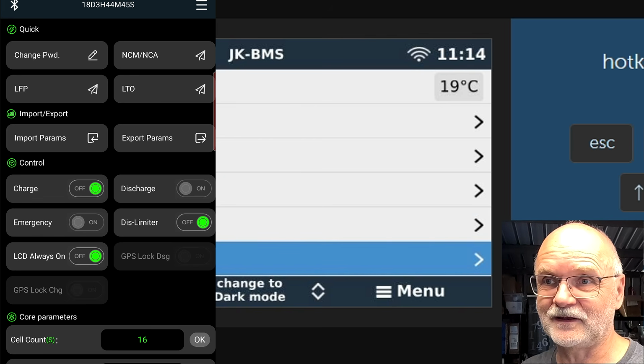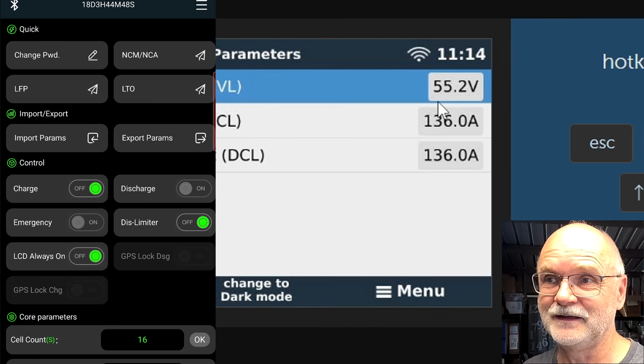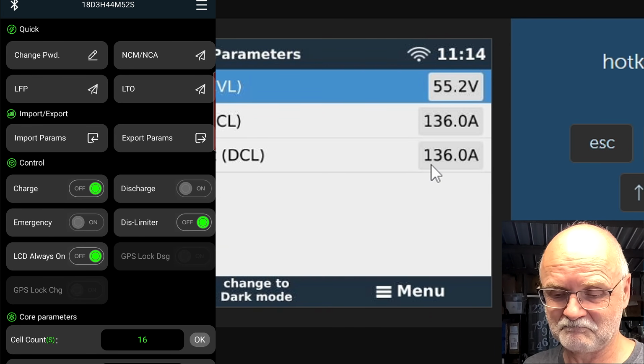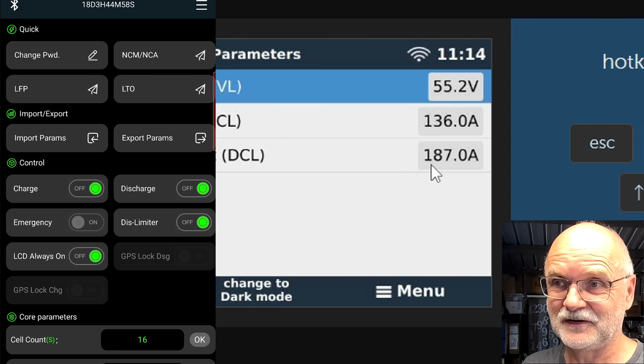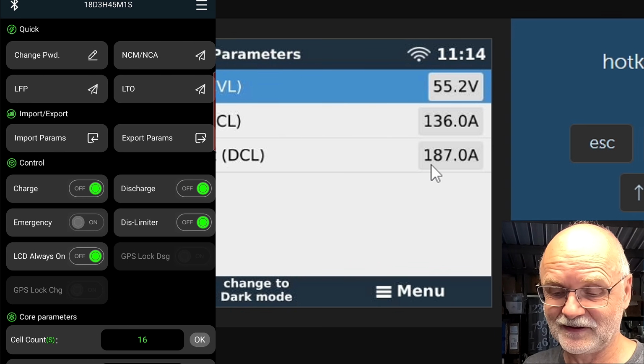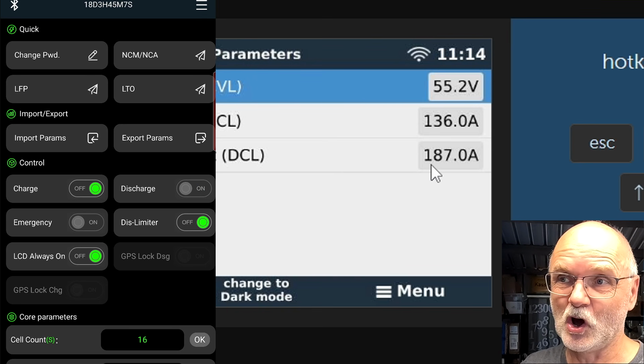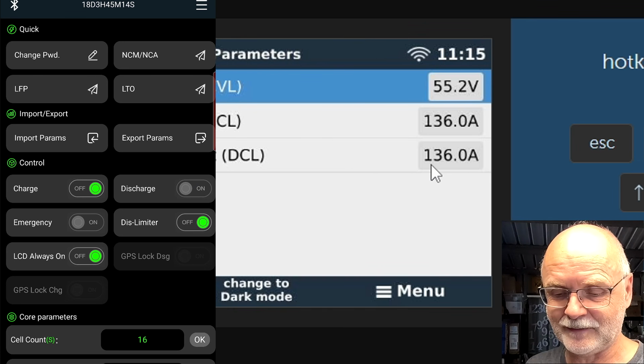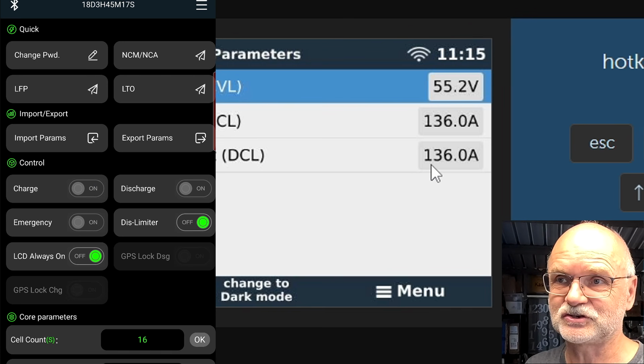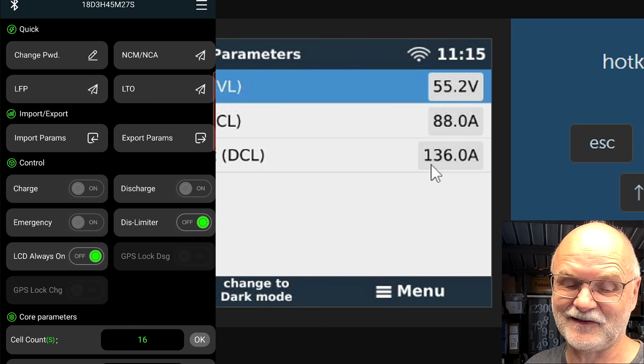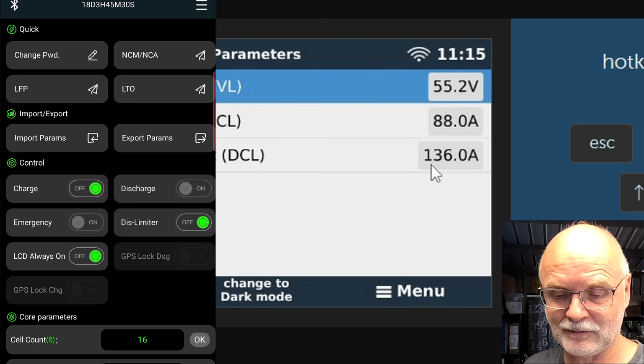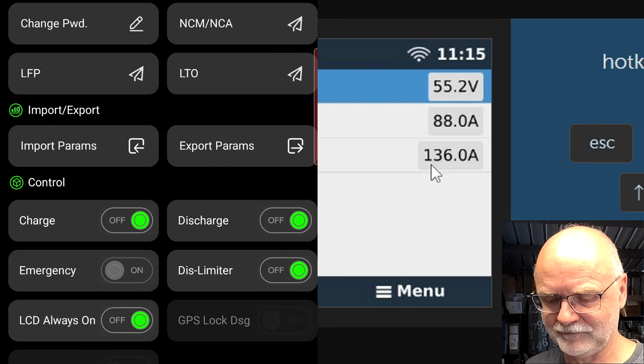And we should also see this reflected in the parameters requested from your inverter. Yeah, see the discharge has come down from, I'll turn it back on, takes a moment. Yeah, 187 amps. And when I disable discharge in one of the BMS, it also allows a lower discharge current for all your battery banks in common then. 136, perfect. And if I disable charge here at the same time, we should see the charge current limit going down from 136 to under 100 something, I don't know. There goes 88 amps. That's the maximum with 2 BMS remaining. So everything works perfectly. Okay, turn this all back on.